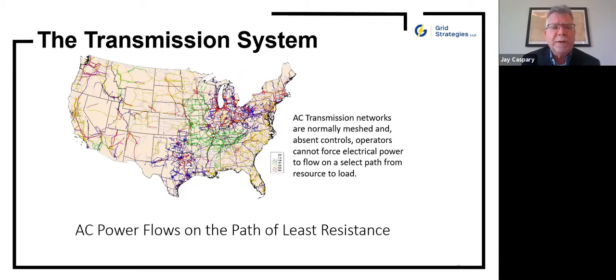So if you've got parallel ultra high voltage or extra high voltage lines, maybe a 345 kV line in parallel with an aging 50-year-old 138 kV system, there's going to be a lot more flow on the 345. But should that EHV backbone line go out of service, the flow transfers onto the underlying 138, which can create problems if the system hasn't been planned appropriately, or if extreme weather drives super high loads, or generators are out of service for whatever reason.